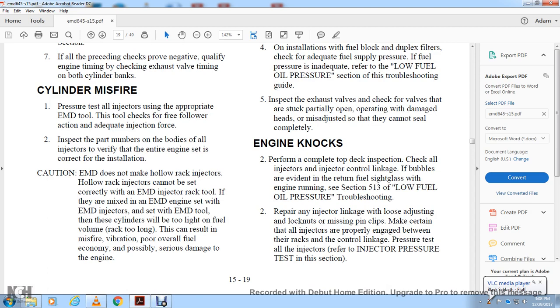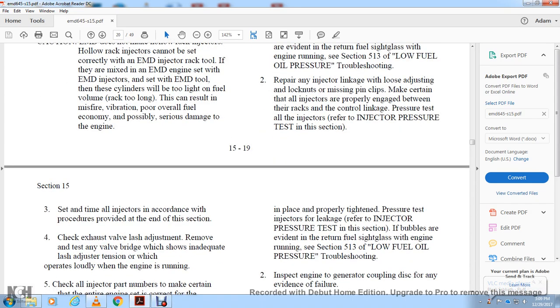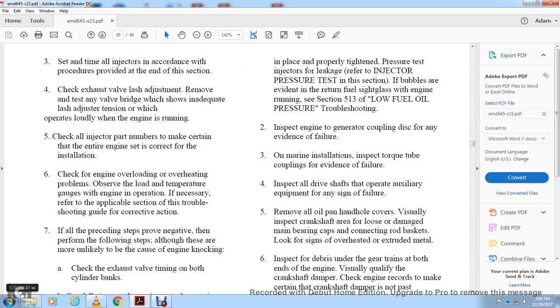Repair injector linkage for loose adjusting — locknuts or missing pin clips. Make certain all injectors are properly engaged between the racks. Pressure test all injectors and refer to the injector pressure test section. Set all injectors according to the procedure at the end of this section. Check exhaust valves for proper adjustment — remove and test any valve bridge that appears to lack proper adjustment, particularly if it operates loudly with the engine running. Check all injector part numbers to make sure the entire engine set is correct for the installation.